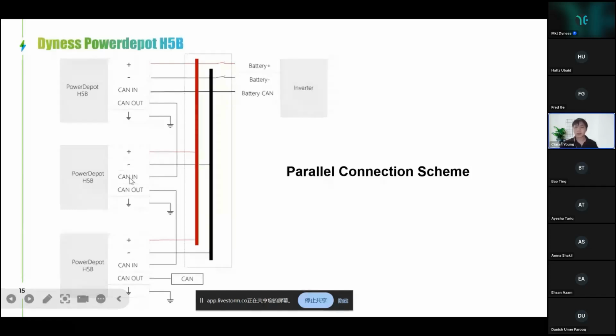For the last slave battery, when there are over 5 pieces in parallel connection, we should put a terminal resistance for better system stability. You may ask how to know which one is the master battery. For Dyness products, the one directly connected to the inverter will be the master battery, and the others will be slave ones automatically, managed by the master BMS.